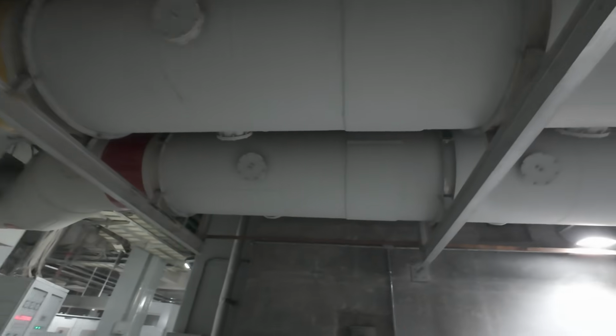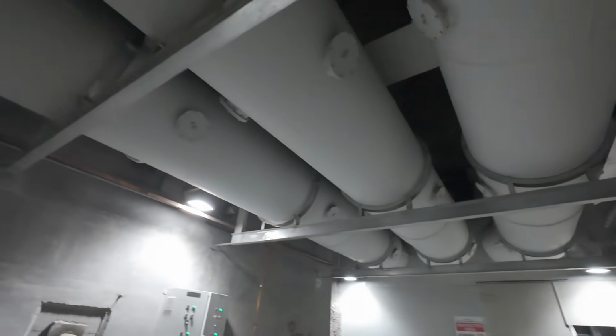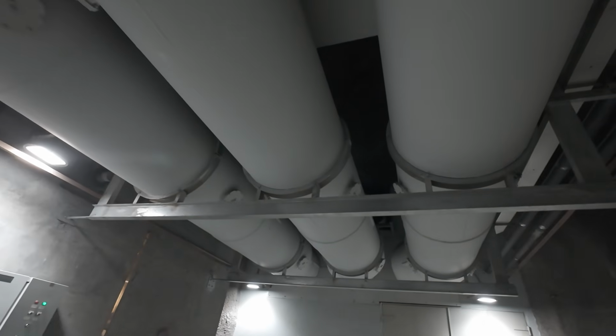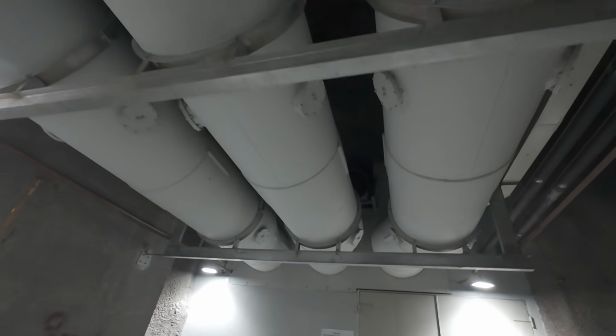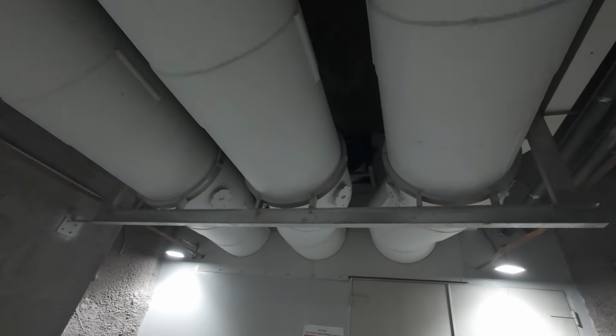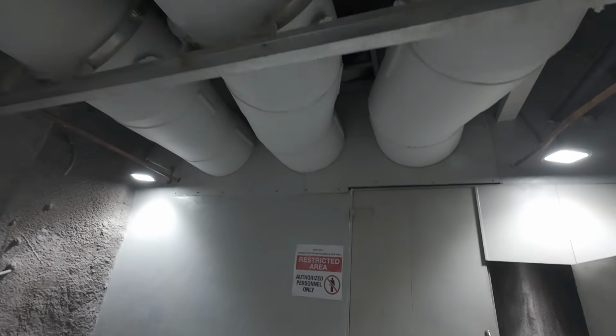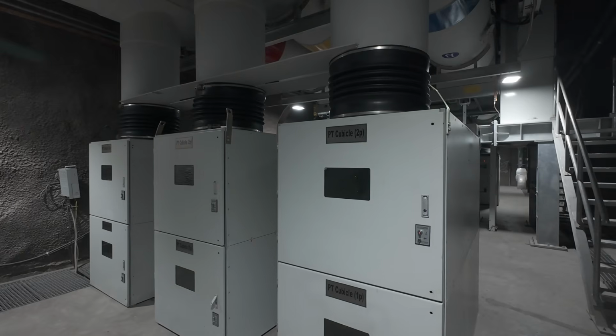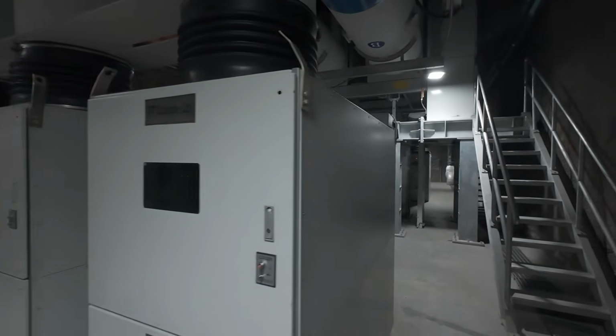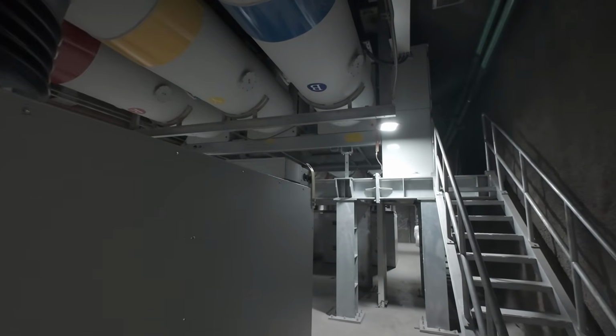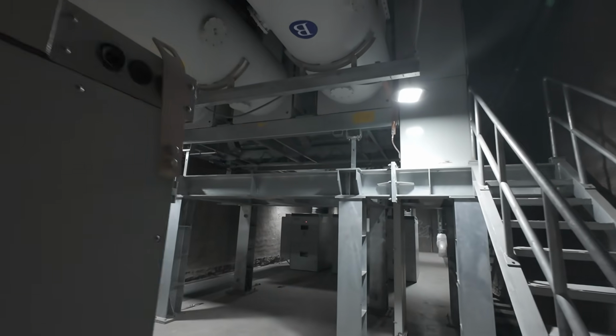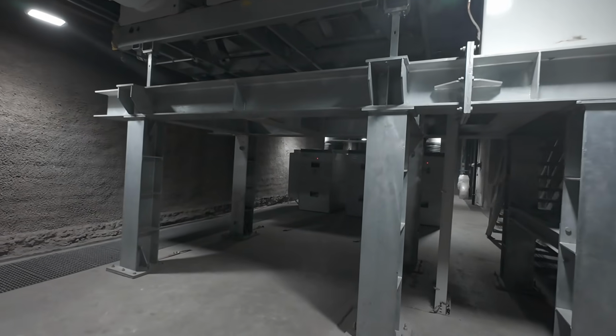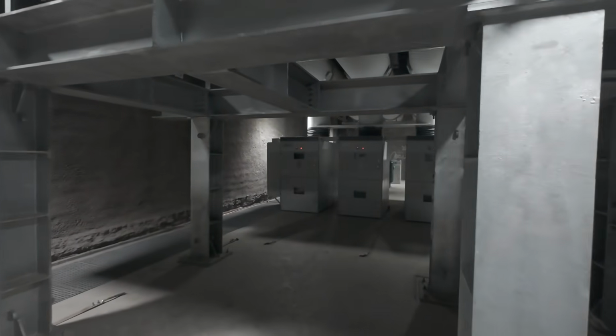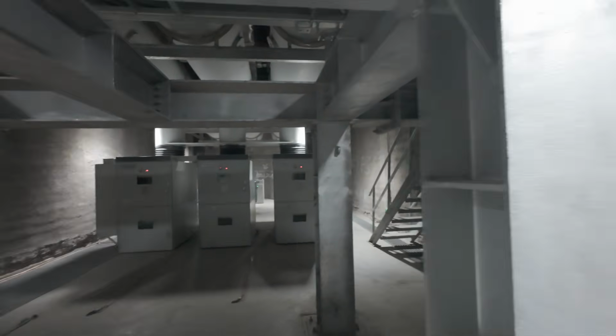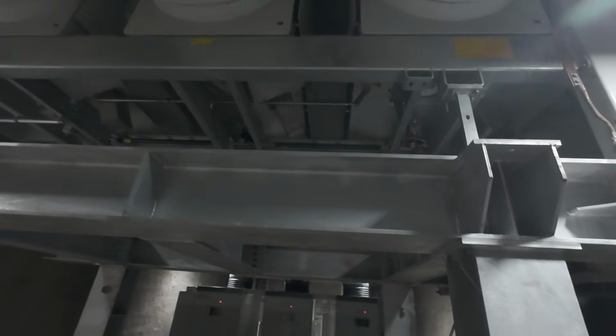Inside a hydro generator, everything happens at massive scales. Huge magnetic field, extreme temperature, gigantic rotating forces. A single mistake can destroy equipment worth millions. That is why the AVR continuously runs advanced protection systems in the background. The overexcitation limiter prevents rotor overheating. The underexcitation limiter prevents loss of synchronization. And the volts per hertz limiter protects the generator core during startup and shutdown.